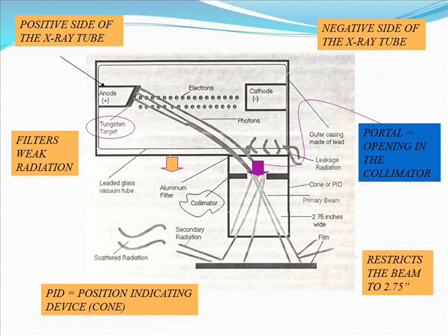So when you push the button and you release the electrons, they immediately shoot over towards the anode. They cannot reunite with the protons. They hit the metal plate that's made out of tungsten called the tungsten target. And that reaction that happens by the electrons hitting the tungsten target, they bounce off and they create radiation, or properly called photons. So photons are the ray produced from the electrons hitting the tungsten target.